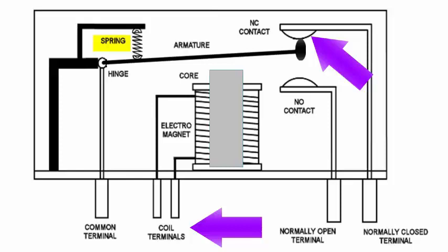Without the spring, if you are using it in an inverted position, then also you will have a gravity issue. So always a spring is used to make sure the effects of gravity are eliminated. Otherwise, you have to use this relay only in the vertical position, or only in the horizontal position depending on its design. But by use of the spring, you can have one single common relay and use it in any position.